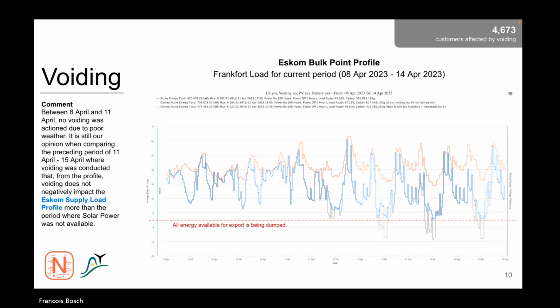Because we're not allowed to export any of the electricity we can access from solar, do you see the gray lines? Those are where, because we're experiencing load shedding, there's reduced demand, meaning we actually switch off and throttle our inverters, otherwise we'd export a megawatt hour back onto the Eskom system. That's what the actual metering profiles show. When load shedding occurs, you can see how we throttle back our inverters - the plant is there, but because of load shedding, and the fact that we can't send that electricity anywhere, we're dumping electricity during those stages for that particular zone that needed to be switched off.